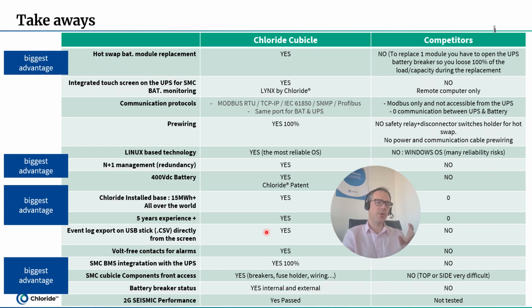We can export from the event log directly from our HMI to a USB stick, the last 2000 events directly from a memory stick. We can also use this USB key to update the firmware and software, which is very convenient for maintenance. We have a volt-free contact for alarms, as I showed you at the bottom of the cabinet.